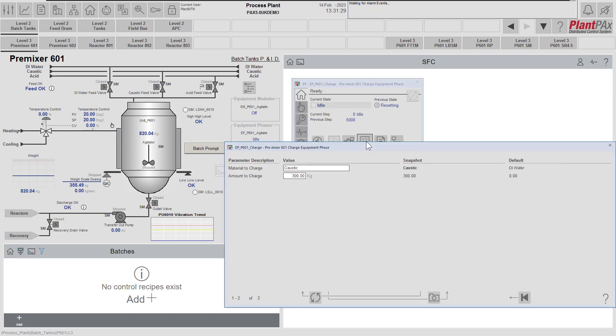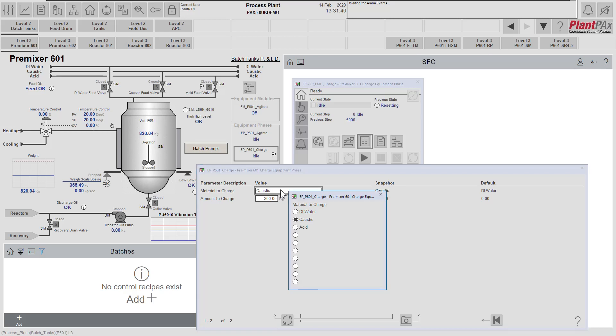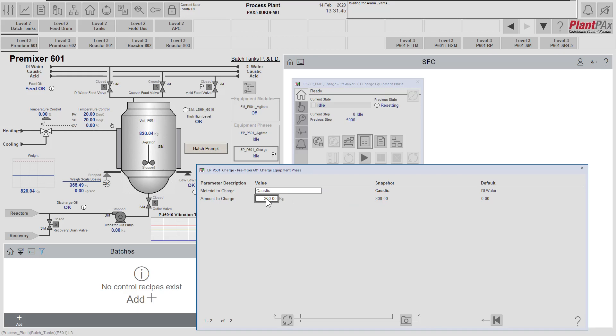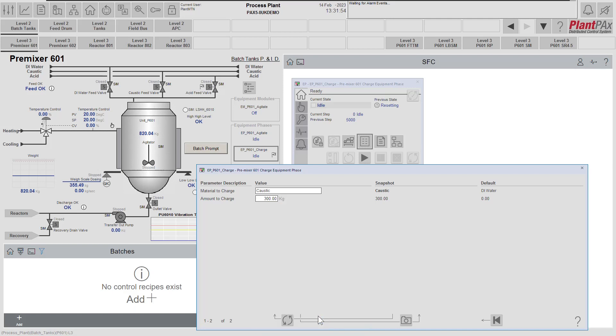From the faceplate we can open up the parameters that have been configured by the implementer for this equipment phase. We can see that there are two parameters available: the material to charge — this is a selection from the valid values, we can only select between DI water, caustic, and acid — and the amount to charge, where you can see there are limits as to what we can enter.